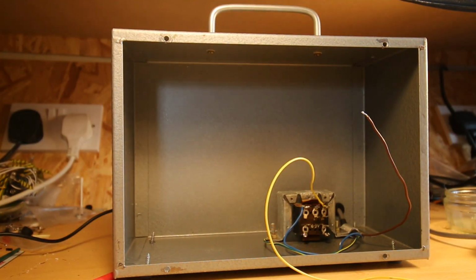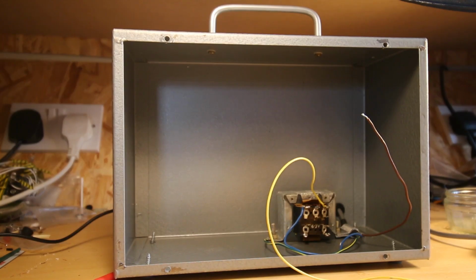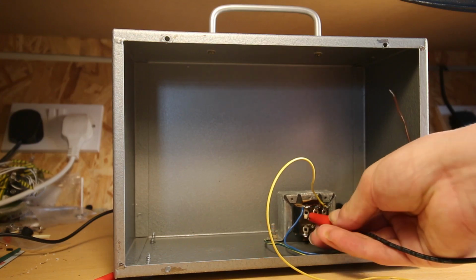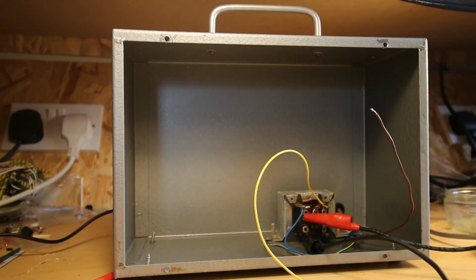Now, with that out the way, what I will bring in, you probably won't be able to actually see the dial on this, so I'm going to have to set it on my lap, but this is my insulation resistance meter. It's quite large, so I will clip one side to the primary, one side to the secondary, like that. I will set this to the lower voltage insulation test for starters.